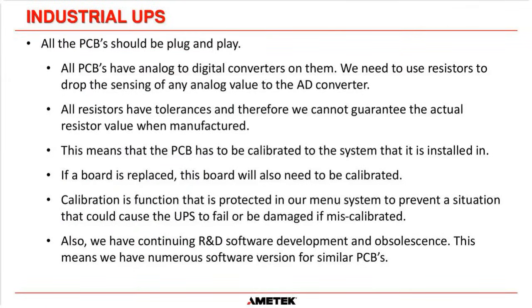And the next misconception is that all the PCBs should be plug and play. And we truly wish that they could be. But unfortunately, there are some circumstances that are out of our control, especially in this day and age, which means they can't be. On a digital system, all PCBs have analog to digital converters on them. We must use resistors to drop the high voltage sensing of any analog value to the analog to digital converter. Our battery is 135 volts DC. We have to use resistors to drop that voltage down to a suitable level, anywhere between 5 and 12 volts, to go into the analog to digital converter or digital to analog converter.